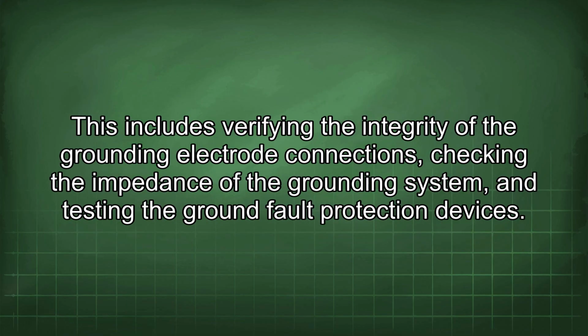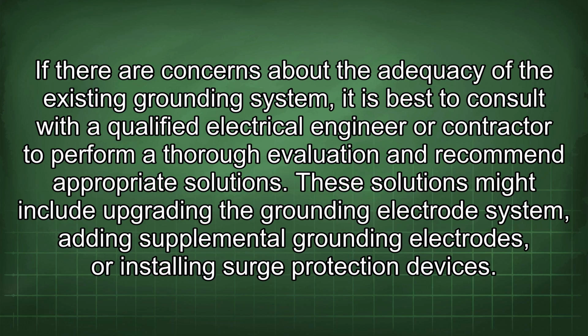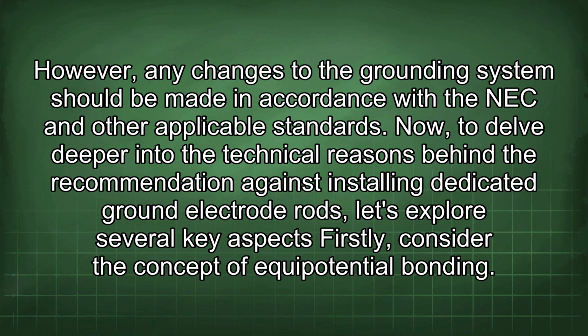This includes verifying the integrity of the grounding electrode connections, checking the impedance of the grounding system, and testing the ground fault protection devices. If there are concerns about the adequacy of the existing grounding system, it is best to consult with a qualified electrical engineer or contractor to perform a thorough evaluation and recommend appropriate solutions. These solutions might include upgrading the grounding electrode system, adding supplemental grounding electrodes, or installing surge protection devices. However, any changes to the grounding system should be made in accordance with the NEC and other applicable standards.